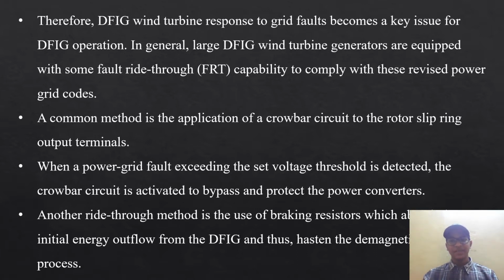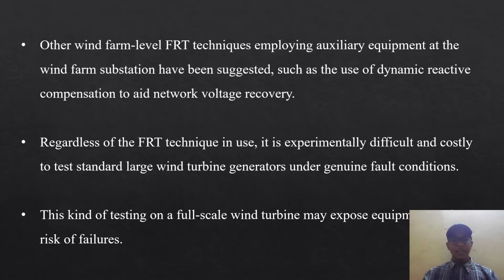In general, large DFIG wind turbine generators are equipped with some fault ride-through capability to comply with the revised power grid codes. A common method is the application of a crowbar circuit to the rotor slip ring output terminals. When a power grid fault exceeding a set voltage threshold is detected, the crowbar circuit is activated to bypass the power converters. Another ride-through method is the use of braking resistors to dissipate the initial energy outflow of the DFIG and thus hasten the demagnetization process. Other wind farm level FRT techniques employing auxiliary equipment at the wind farm substation have been suggested, such as the use of dynamic reactive compensation to aid network voltage recovery.